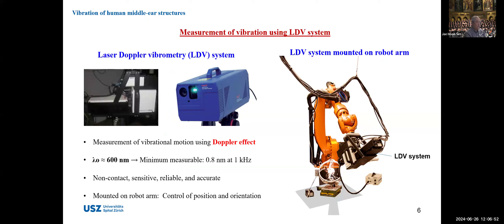One of the methods widely used to measure this vibrational motion is the laser Doppler vibrometer, or LDV system. This LDV system uses the Doppler effect to measure vibrational motion, and the minimum measurable amount is about 0.8 nanometers at 1 kHz. This method provides non-contact, sensitive, very reliable, and accurate measurement, and is one of the most widely used approaches to measure vibrational motion of middle ear structures.